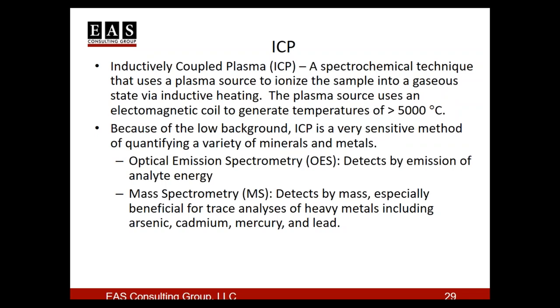ICP is the same sort of technique, but instead of using a flame, we use a plasma, and that gets much hotter—over 5,000 degrees Celsius. That plasma heats up the samples, and because you've removed a lot of the background, it's so high that you have much better sensitivity for the minerals and metals. So this is really great for trace analysis of heavy metals.